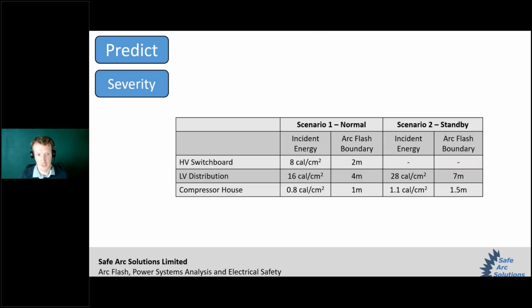So once the study is done, all that data is processed and the calculations are run, you're going to be given some results. And the two key things that you're going to be told about in terms of severity are your incident energy and your arc flash boundary at each of these pieces of equipment. On the screen is a simplified set of results. Basically, we've just distilled it down to the important information, and this shows it for two different scenarios: the normal, where you're fed from your site supply, from your external grid, and a standby scenario where maybe that has been lost, so you've switched over to the standby generator.